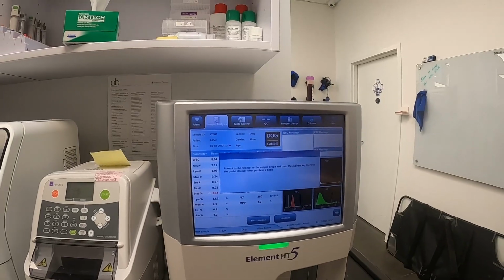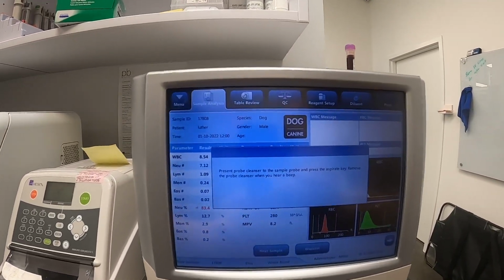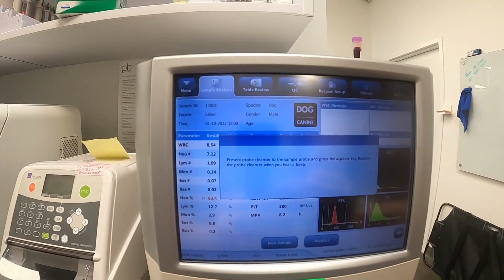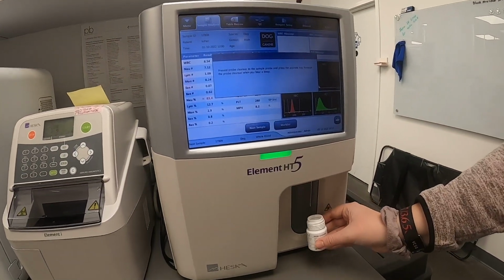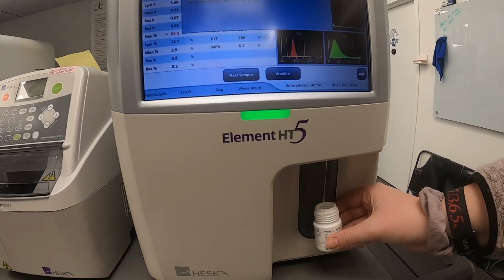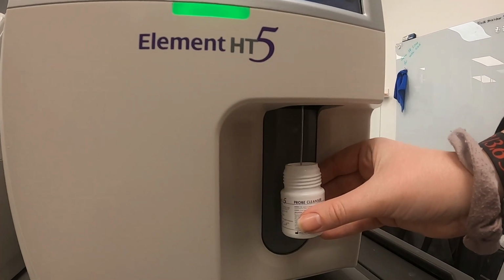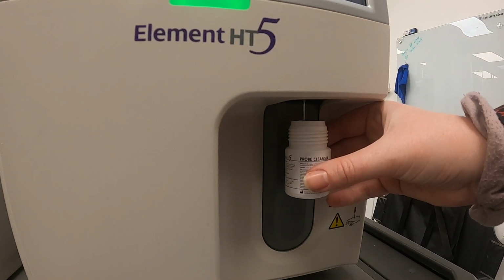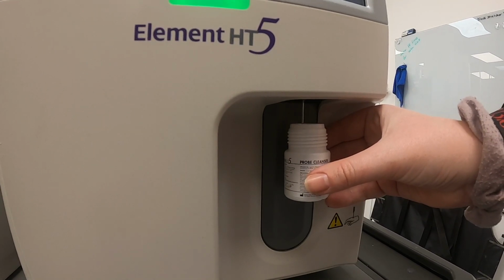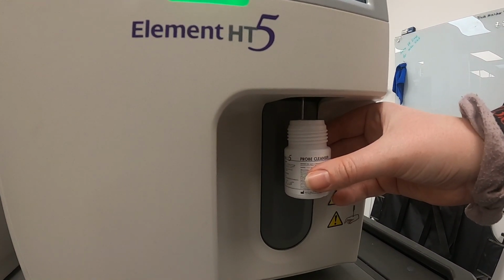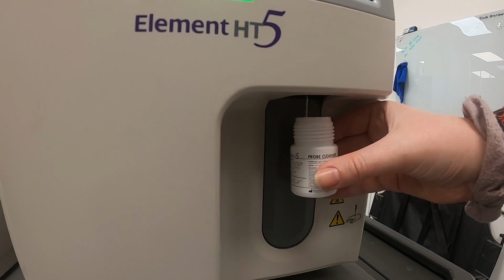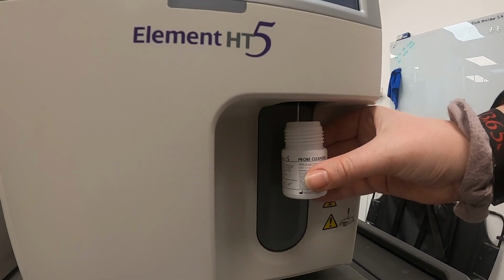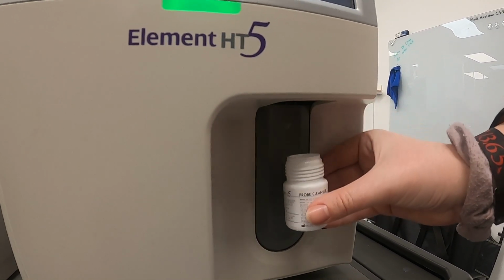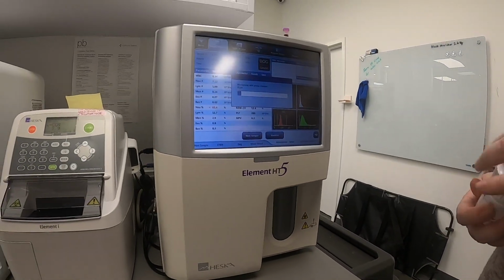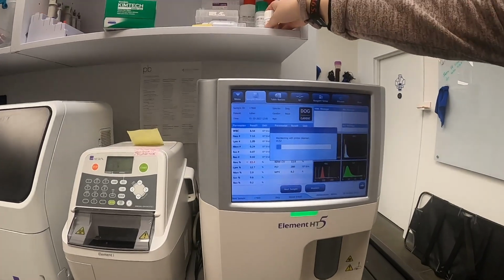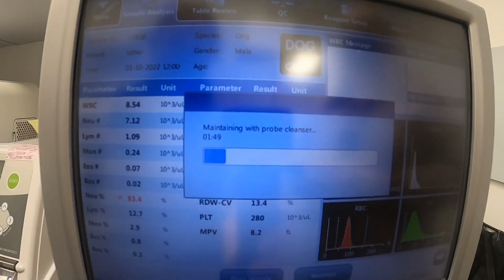So at this point, a message will pop up that says present probe cleanser to the sample probe, and press the aspirate key. So we're going to uncap our probe cleanser. The sample probe is this long metal probe here. We're going to introduce our probe cleanser. We don't want to touch the bottom of the bottle, but get close to the bottom where the fluid is located. And while your bottle is here, you're going to press the aspirate key on the back. And you're going to hold your bottle until you hear a beep, and you are good to move. And this takes about 2 minutes for the probe cleanser to do its job, and then we'll be ready to run our sample.